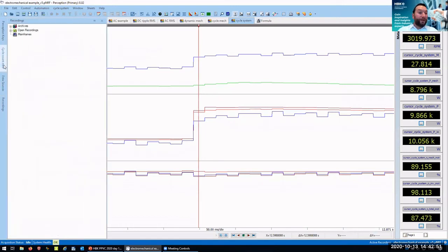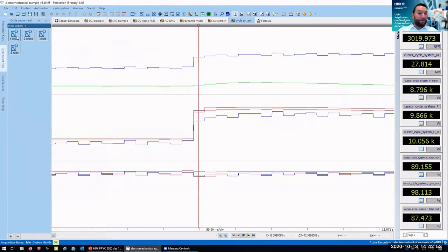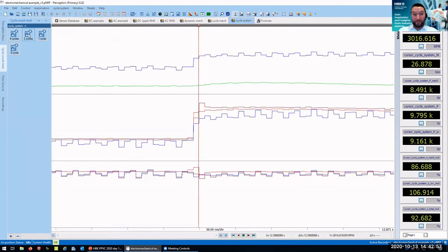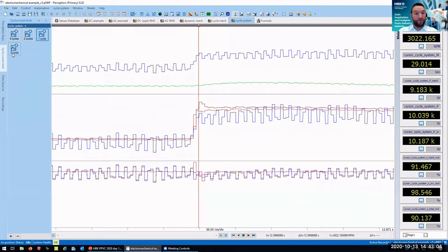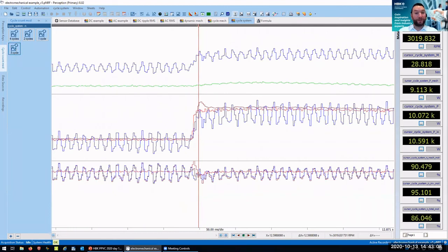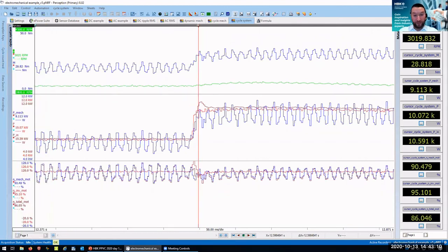So if I now change my cycle count, which is currently 4, to 2, for example, we instantly see our calculation rate is updating, and we see more dynamics in our signals. So we can even go back to 1 cycle based, or the most dynamic power measurement of a half a cycle. And in that case, again, we see the dynamic behavior of the machine coming back in. We see the machine going from generator to motor, from generator to motor. So we see some efficiencies over 100%. But as we know how our system is calculating this, we can understand it.